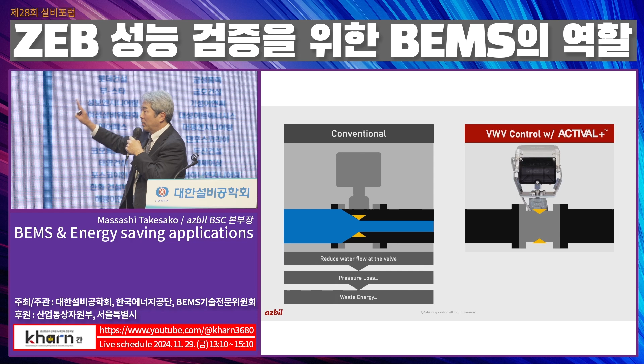It is very, very difficult to understand, but this is the image of the valve of the AHU, not the chiller side. AHU side. The AHU has a control valve. This is the conventional method. In the conventional method, if the load decreases, the valve will react to minimize the water flow. In order to maintain the room condition, the valve will start to close. This is a very simple explanation, but this is actually wasting energy. So our target is that we try not to close the valve. In order to keep the valve open, how can we do that?